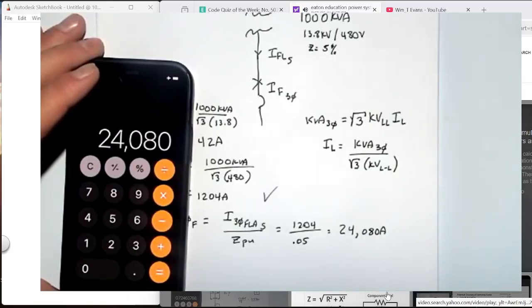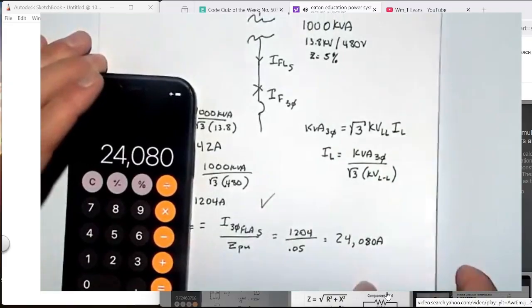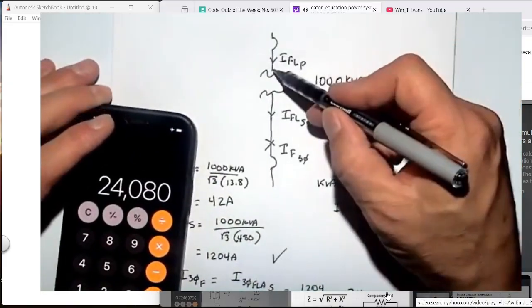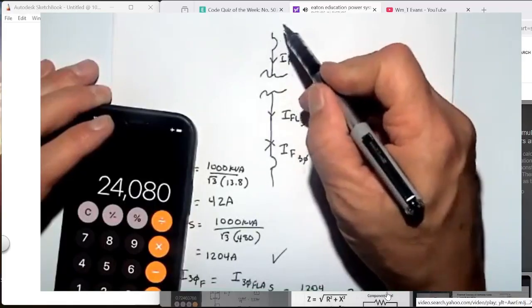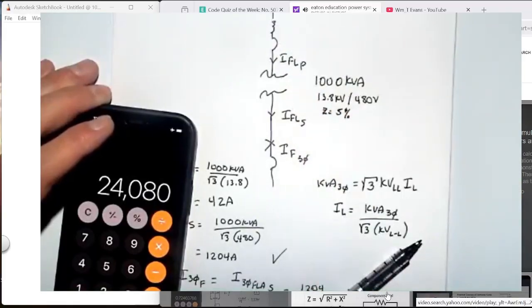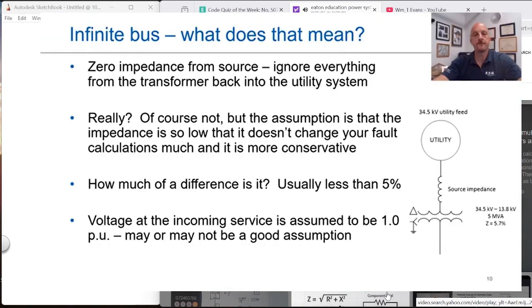Now, on the next page, we're going to talk about the infinite bus and why we do not calculate the fault current on the primary side. The reason we can't is we don't know what the impedance back here is. So what does an infinite bus mean? An infinite bus basically says that we have zero impedance all the way looking back to the source. And we know that's not exactly true. Of course it's not true. But if it's low enough, the calculations work out so that we can ignore the impedance of the upstream transformers and cables and everything else, and just use the nearest upstream transformer as our main source impedance.